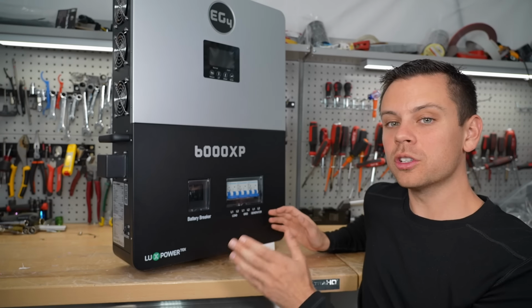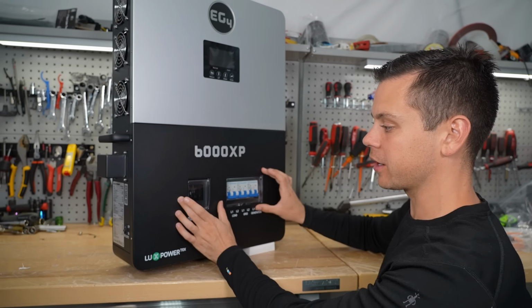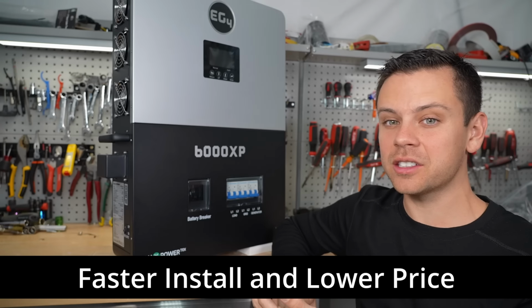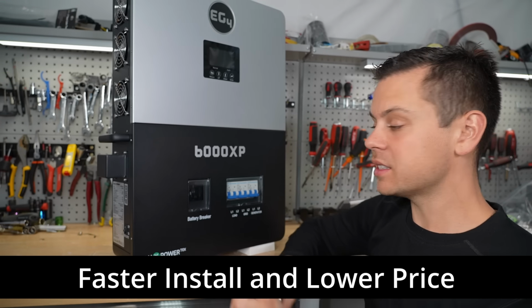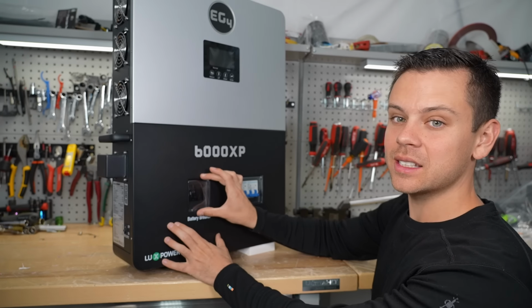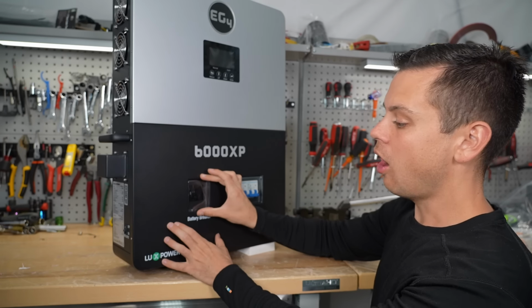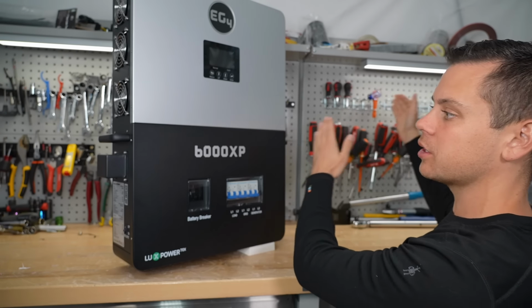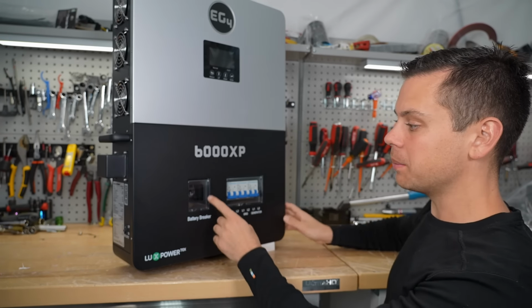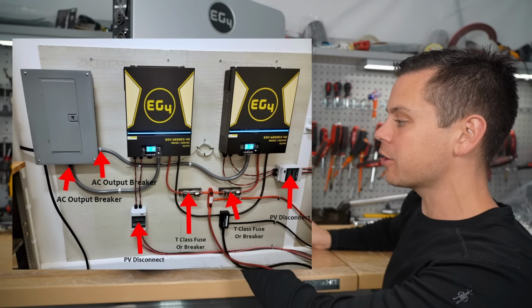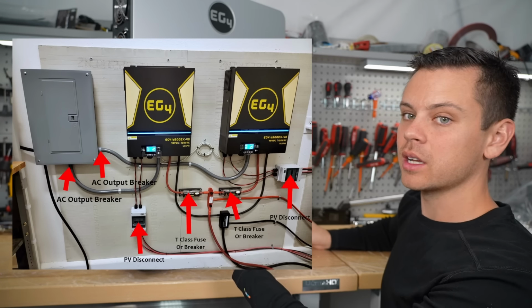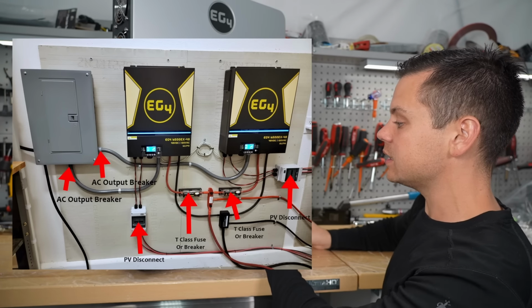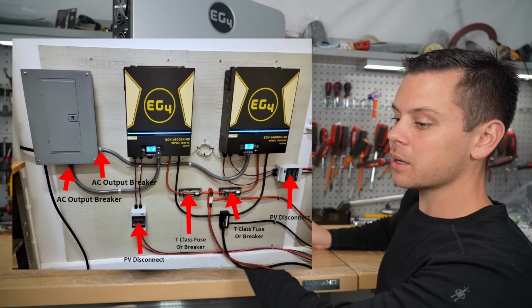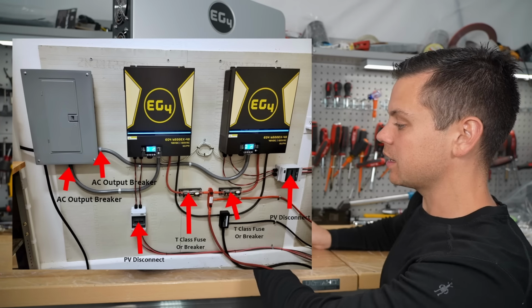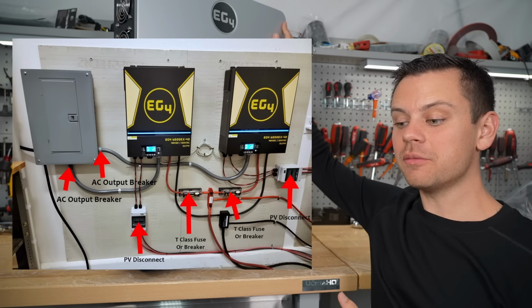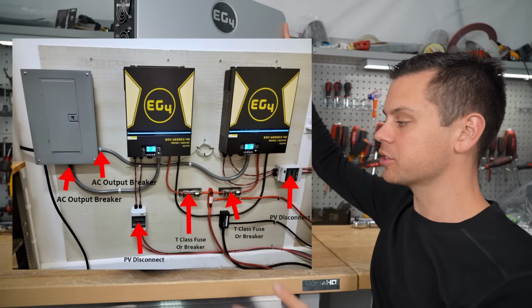Next, unlike the older models, this one has its own circuit breakers, and this makes installation faster and cheaper, because these are not cheap, especially DC rated resettable circuit breakers. On older models, if you had multiple units on your wall, for each unit you had to buy your own T-class fuse for the battery connection or a resettable DC rated circuit breaker, and then for each AC output you had to supply a circuit breaker at the load center where you connected them all together. That costs a lot of money, and you have to wire all of that stuff up yourself.